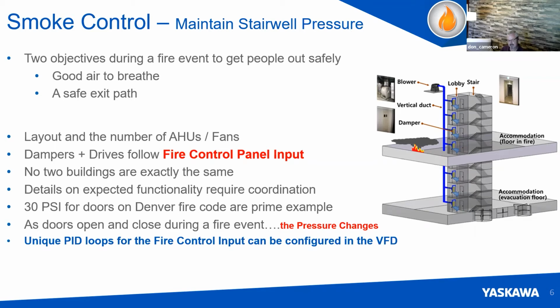So the key is that dampers and drives work together to follow that fire control panel input, in combination with the transducers that feed back, to do whatever it is you want to do. Again, reverse speed, maintain pressure, run at a set speed, whatever you want to do. For example, one unique characteristic of the Denver Fire Code is a 30 PSI to be able to open the door to get out. But as the event is occurring, different doors open, so pressure changes throughout that building, and now you have to adapt. So that's why drives are so critical in that, because they can adjust the speed based on those changing pressures. And you can even have a unique PID loop for the fire control panel.